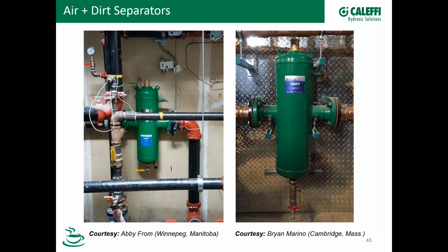Sure. Well, maybe from a purist standpoint, you'd want to put an air separator on the hot supply pipe and put a dirt separator on the return to the boiler, especially if you have a high efficiency boiler that's very sensitive to dirt. That might be the ultimate way to go, because then you're scrubbing out that dirt before it gets into the small passages and sensitive areas in a high efficiency boiler. But a lot of times that's just inconvenient.